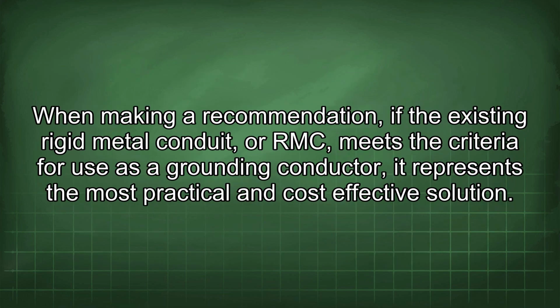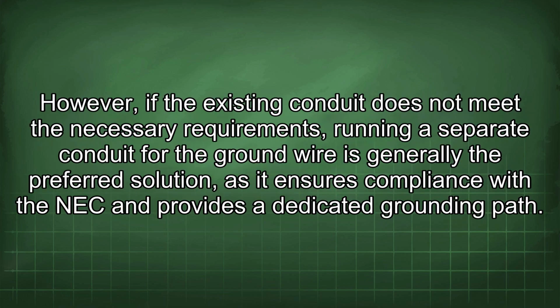When making a recommendation, if the existing rigid metal conduit, or RMC, meets the criteria for use as a grounding conductor, it represents the most practical and cost-effective solution. However, if the existing conduit does not meet the necessary requirements, running a separate conduit for the ground wire is generally the preferred solution, as it ensures compliance with the NEC and provides a dedicated grounding path.